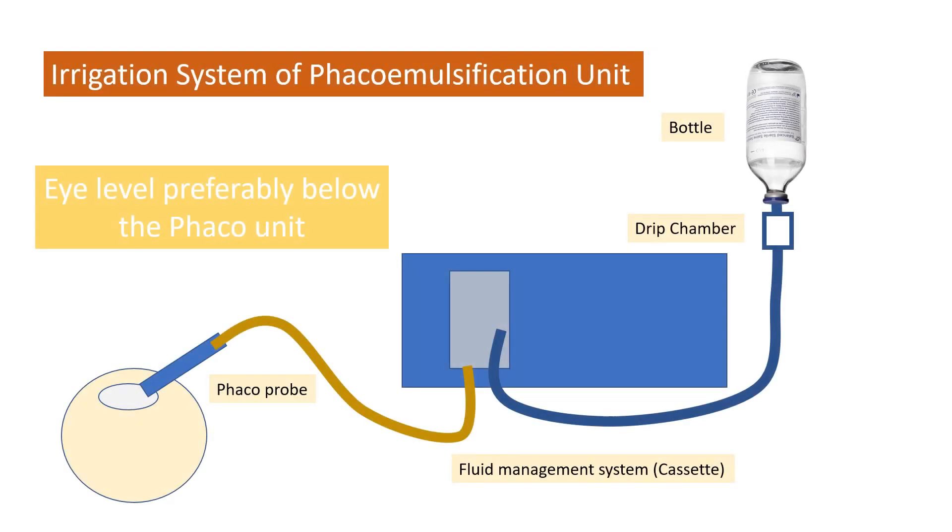Let's have a look at the irrigation system of the Phacoemulsification unit. It starts with the bottle, followed by an IV set which has an important structure called the drip chamber, then it goes into the fluid management system which we call the cassette, and from there the irrigation line goes into the Phaco probe and into the eye.